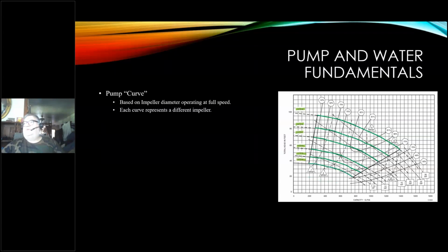This pump can use all of these impellers. You just have one installed per pump, but you have to remember which one you're dealing with, because they sometimes will stamp it on the nameplate, not always. This same casing can handle this family of six impellers, so you can have whatever you want put in here.